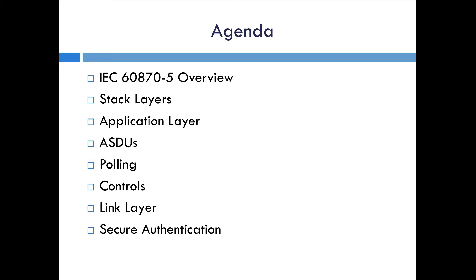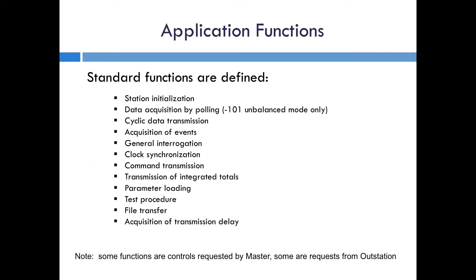Let's dig in and look in a little more detail at the application layer. Within the application layer, the standard identifies something known as application functions. These are basically the requests which can be sent either from the master or the outstation. There's an initialization sequence which the master controls, and data acquisition by polling — though that's a little misleading because this is just for 101 unbalanced mode. The other common ways for the outstation to send data are through cyclic data transmission, which is for static data, and acquisition of events, which is for sending event data or data changes. And then there's the general interrogation that we briefly talked about before.